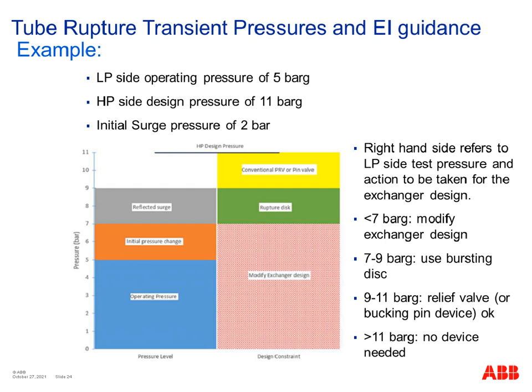So you're talking about modifying the exchanger design. But bear in mind that if you've got an LP side with a 5 bar operating pressure, you would normally hope that the test pressure would be more than 7. But if it's less than 7, then you may need to modify the exchanger design. If it's greater than 7 but less than 9, then you'd be in the position of wanting to use a rupture disc to protect the LP side from the case of tube failure.